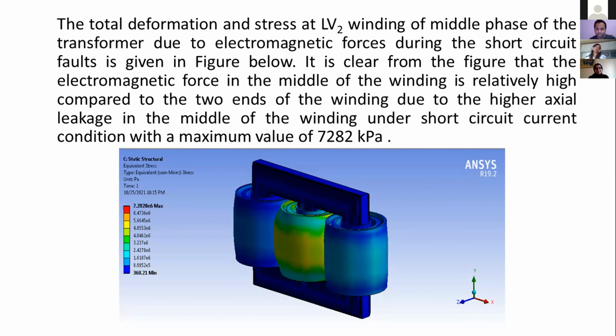The total deformation and stress at the outer LV winding of the middle phase due to the electromagnetic forces during the short circuit faults is given in the figure. It's clear from the figure that the electromagnetic force in the middle of the windings is relatively high compared to the two ends of the winding due to the higher axial leakage in the middle of the winding under short circuit condition, with a maximum value of 7282 kilopascal.